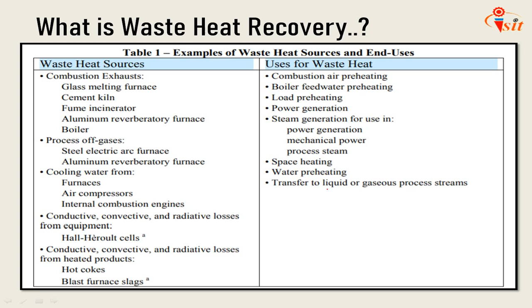Another advantage of waste heat recovery is that it can reduce capacity requirements for facilities and thermal conversion devices, leading to reduction in capital cost. For example, consider the case of combustion exhaust gases used to heat building air for space heat. In addition to replacing purchased fuels, the recovered waste heat can potentially eliminate the need for additional space heating equipment, thereby reducing capital and overhead cost.